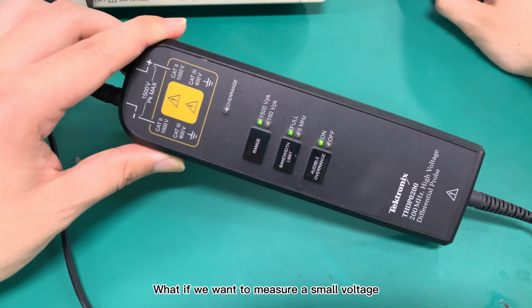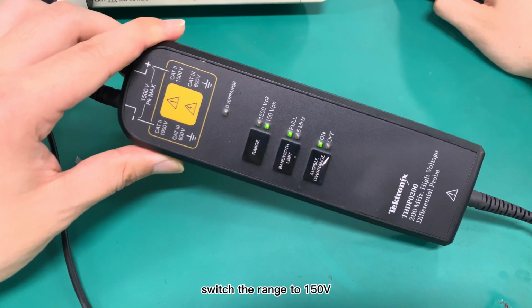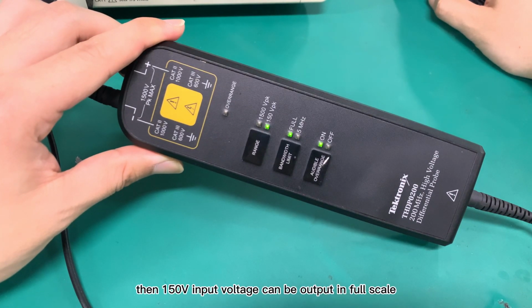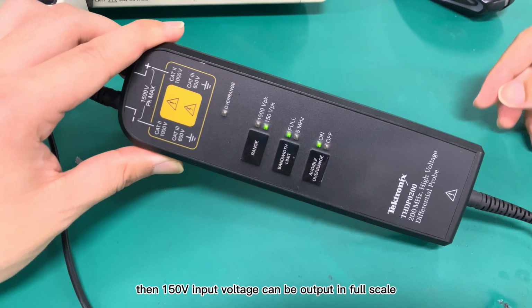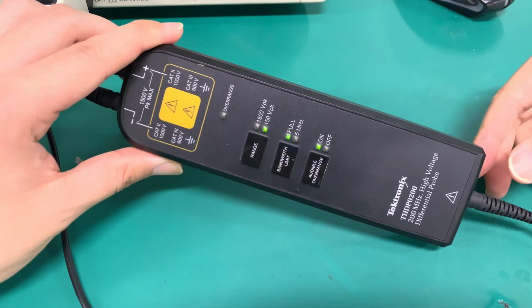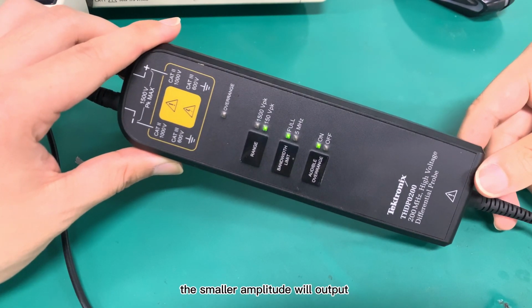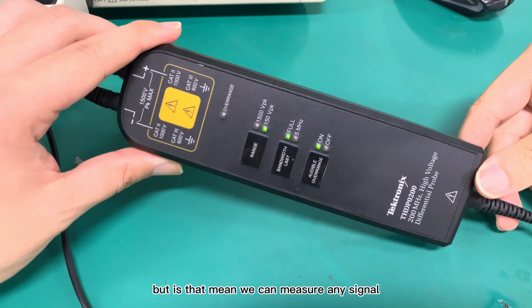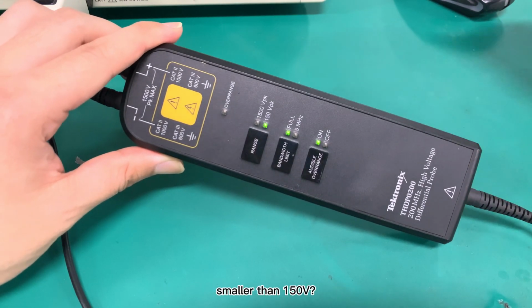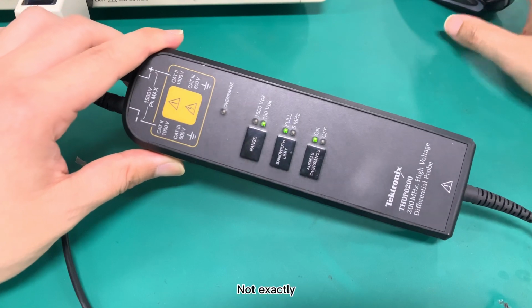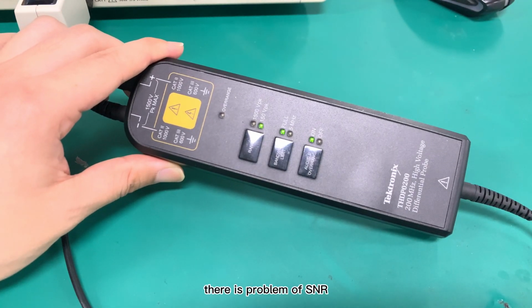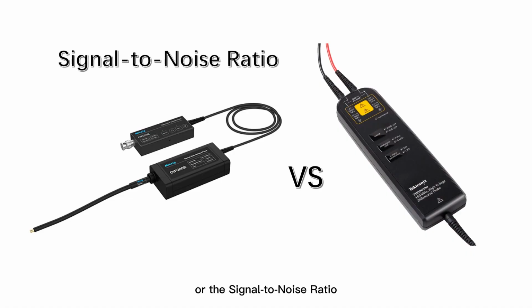What if we want to measure a small voltage? Switch the range to 150 volts. The 150 volt input voltage can be output in full scale. The smaller the signal is, the smaller the output amplitude will be. But does that mean we can measure any signal smaller than 150 volts? Not exactly. There's a problem of SNR, or signal-to-noise ratio.